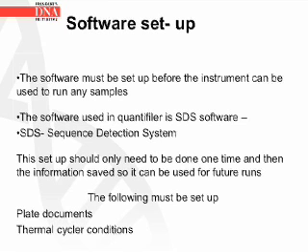Now that the instrument is ready to go, the next step is to set up the software on the instrument. The software must be set up before the instrument can be used to run any samples. The software used in Quantifiler is SDS software. This stands for the Sequence Detection System. This setup should only need to be done one time, and then the information saved so it can be used for future runs. The following must be set up: plate documents and thermal cycle conditions.